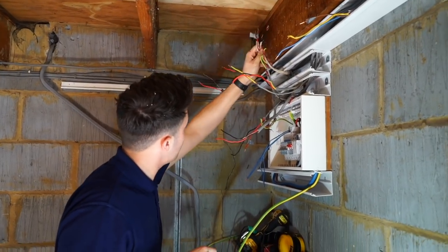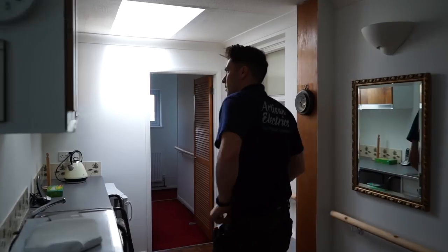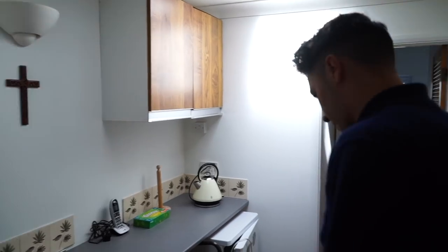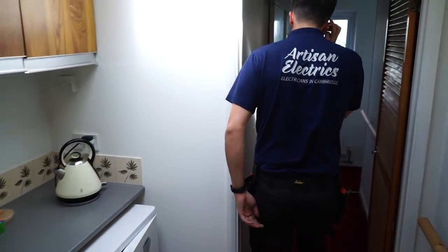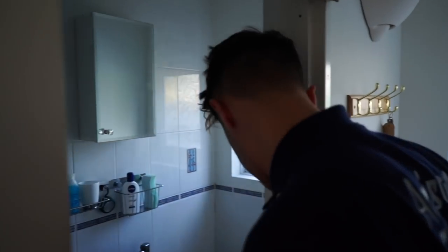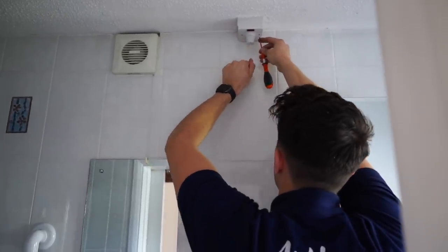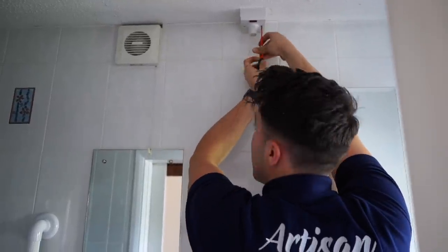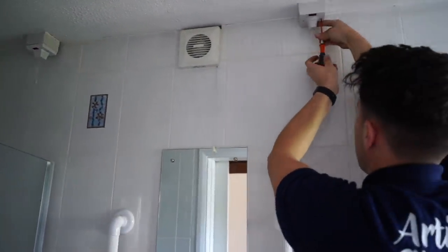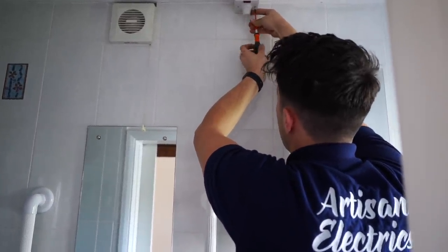You're not doing a fan, you fraud - six mil to do a fan, I'm not buying it. Let's have a little look inside. There's no fan in here, that's the thing, so why am I going for bigger six mil running to something? There's nothing in here that I can reasonably say we need a six mil for, unless it goes into - I reckon it does that - because it doesn't even work. But that one there is the shower, so we've already sussed that. If this other one is spare, I'm just going to cut the cable out because it's an absolute disaster.